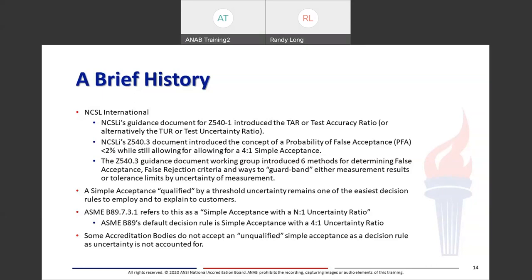In ASME B89.7.3.1, this is referred to as simple acceptance with an n-to-1 uncertainty ratio. The simple acceptance with a 4-to-1 ratio is ASME B89's default decision rule for its standards. If any of you do mass calibrations, OIML, NIST, and ASTM have a 3-to-1 uncertainty ratio for mass calibrations, and that's been the norm for many years. Some accreditation bodies, especially overseas, do not accept what I call an unqualified simple acceptance decision as a decision rule since the uncertainty is not accounted for at all — the old ILAC G8 shared risk idea where it doesn't limit the uncertainty of the measurement.